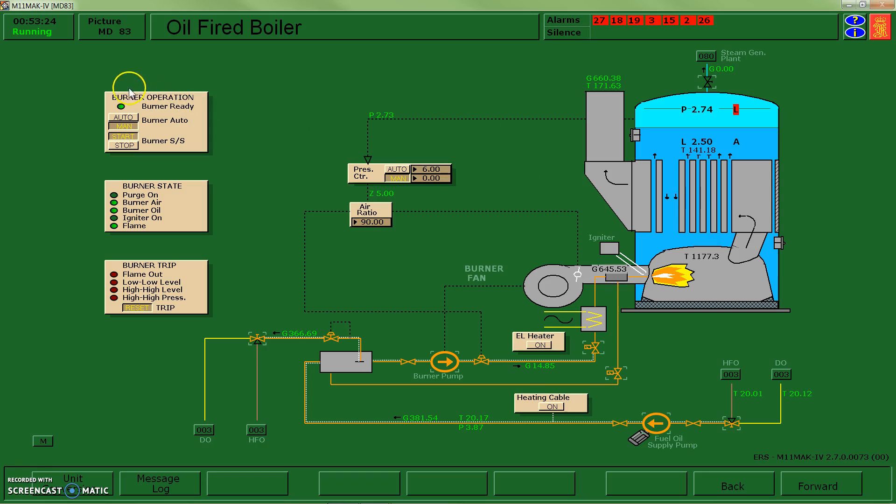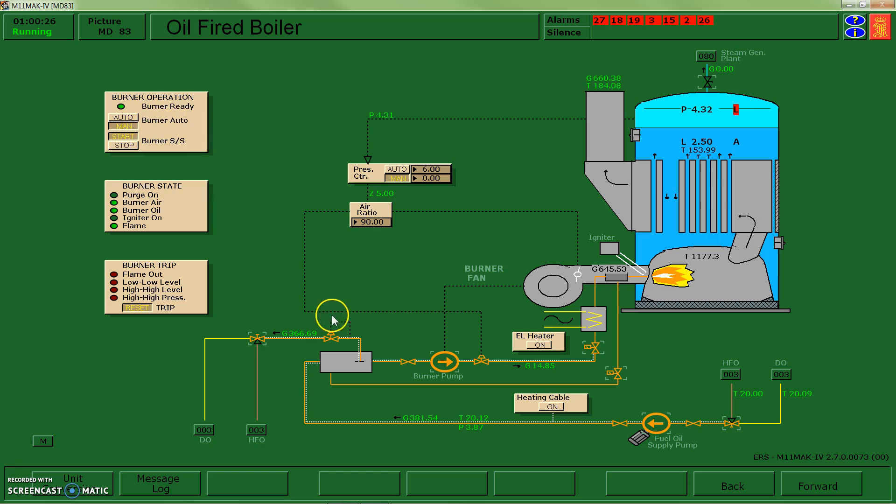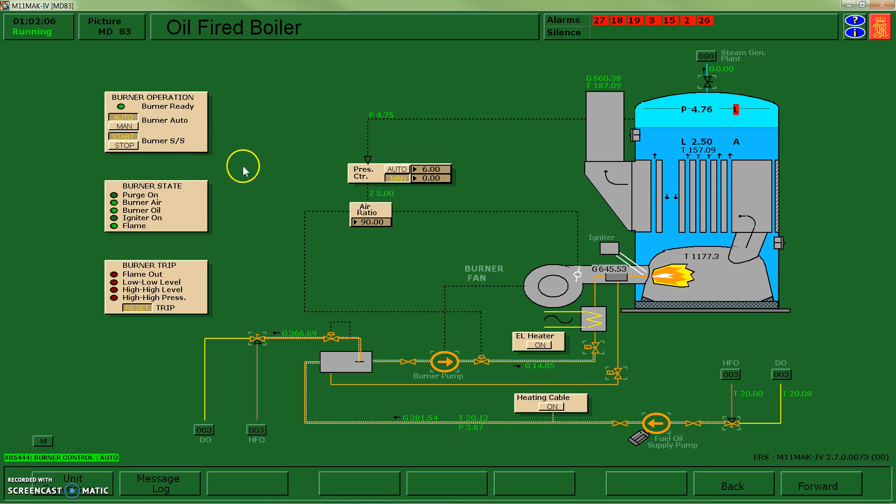You can see over here in my burner operation box, it says burner operation, burner is in auto. Auto means that it's going to make decisions whether to turn on or off the burner. So if the pressure gets too high, it's going to turn itself off. If it's too low, it'll turn itself back on. Right now my system is set up, other than my auto controller for pressure, I'm going to turn it into auto.